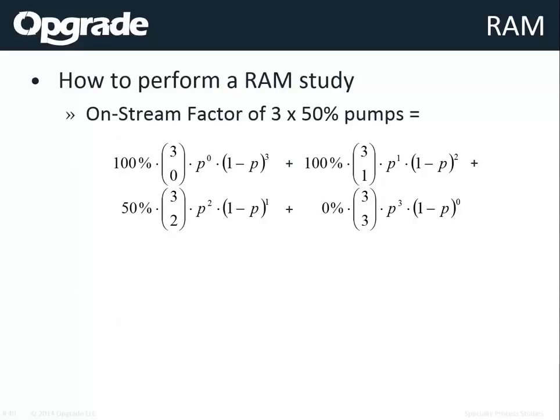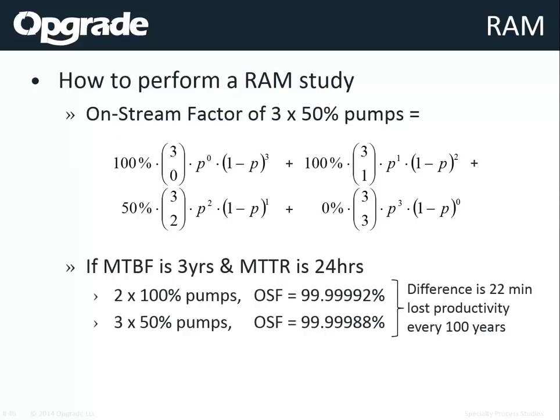Using the binomial combinations — three choose zero, three choose one, three choose two — if none of the 50% pumps are offline, production is 100%; if one is offline, you're still at 100%; if two are offline, you're at 50%; if all three are offline, you're at 0%. Adding it all up: two pumps at 100% gives 99.99992% on-stream, and three 50% pumps gives 99.99988%. The difference is only about 22 minutes of production over 100 years — effectively identical reliability. Unless there's a significant difference in reliability between the pump types, three 50% pumps is a clear, lower-cost solution.